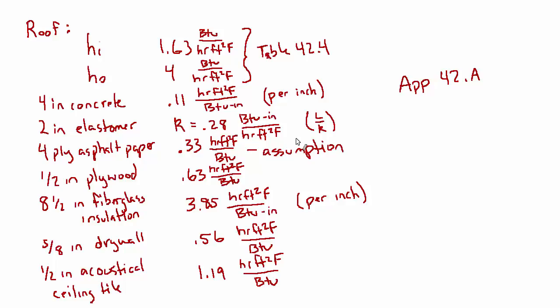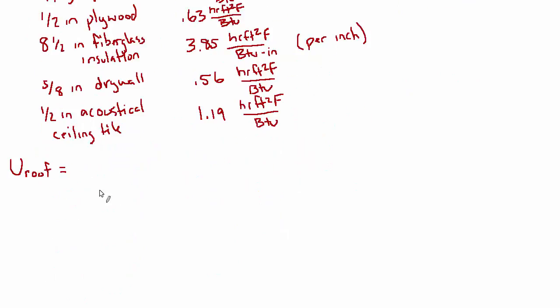So now we're ready to find the overall heat transfer coefficient for the roof. This is going to be a long formula, so let's see if I can get it all on one line. It's going to be 1 over, we have the film coefficients, so 1 over 1.63 plus 1 over 4.